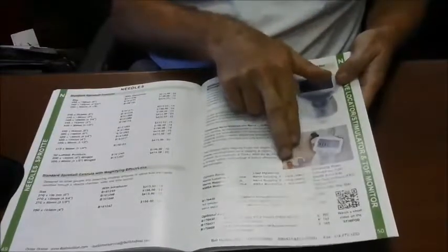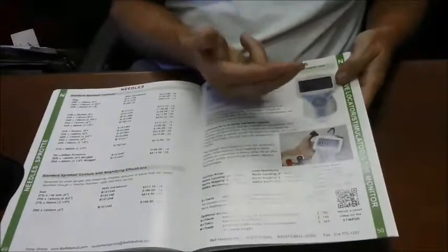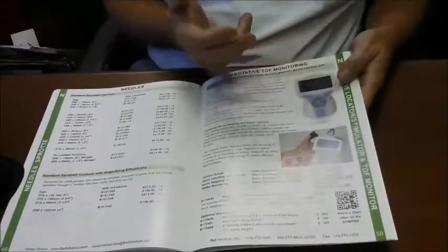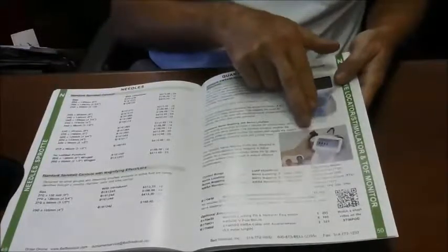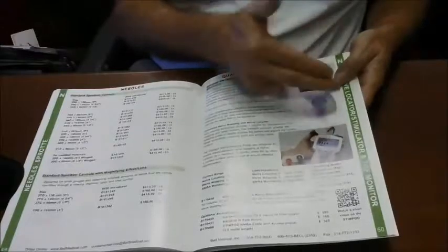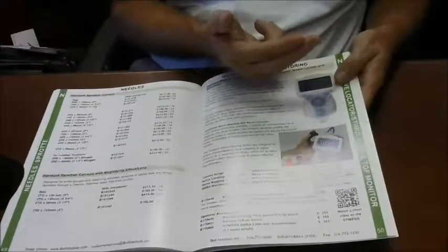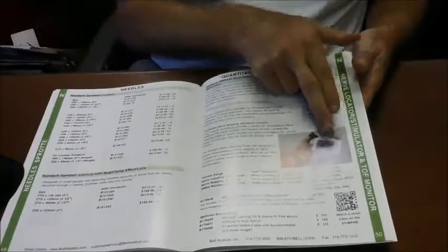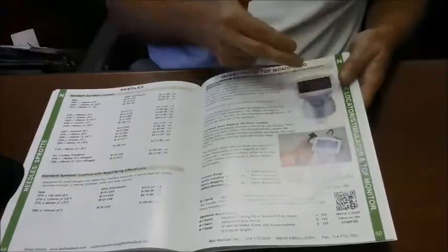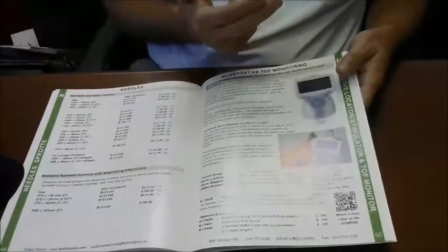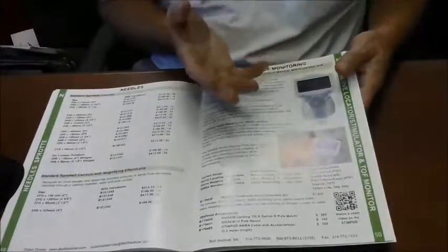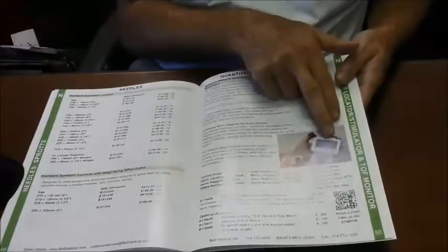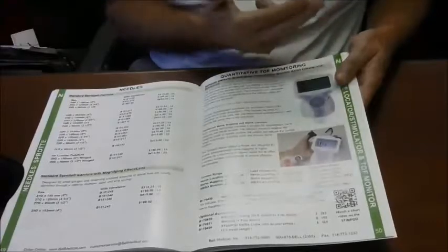When it fits on the thumb, you basically stimulate the ulnar nerve. And what you do is you get thumb movement, and the accelerometer measures that thumb movement and basically gives you percentages. So you'll see a series of bar graphs showing the 4 twitches. If the patient is completely paralyzed, the thumb won't move and it'll display 0 of 4. Then if you get 1 twitch, it'll display 1 of 4, 2 of 4, 3 of 4. Once it gets to that 4th twitch, it measures that 4th twitch compared to the 1st twitch, and that gives you a percentage. So if the 4th twitch is equal to the 1st twitch, that means that patient is almost no longer paralyzed, and they would get a number like 93%. And anything over 90% means that patient can be extubated safely.